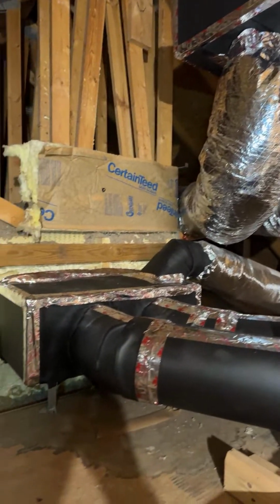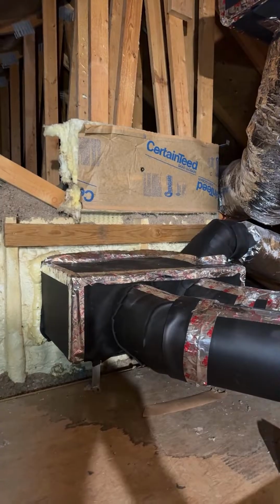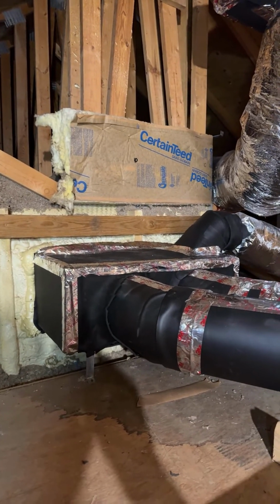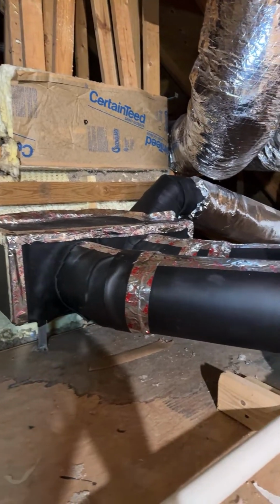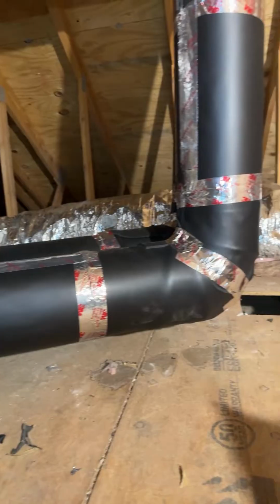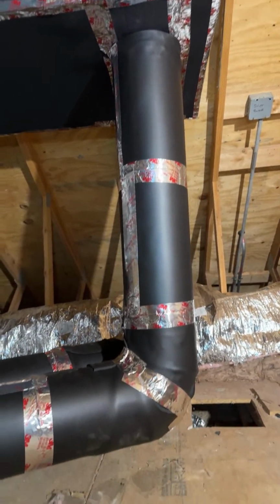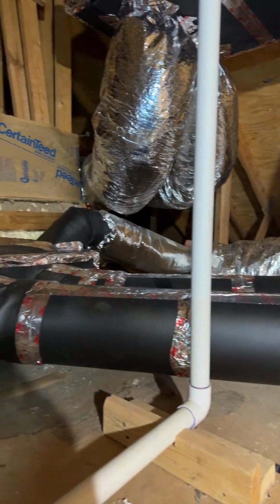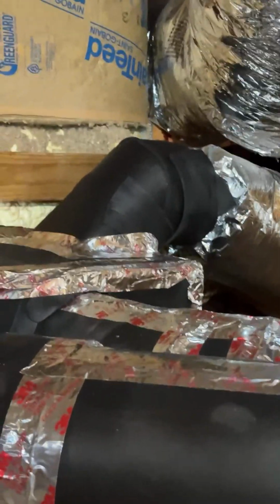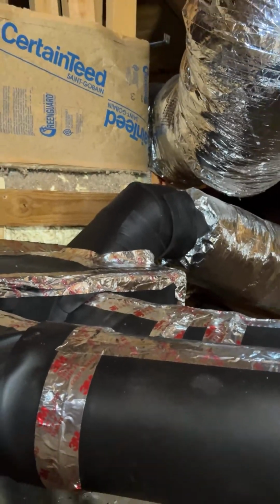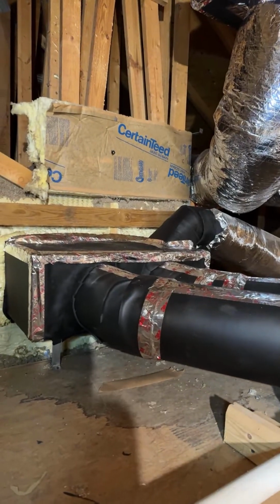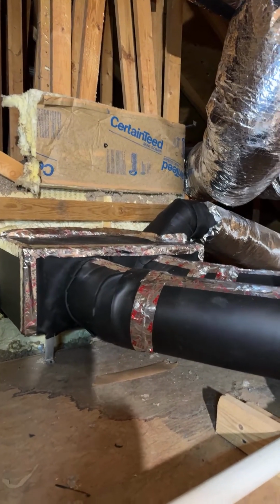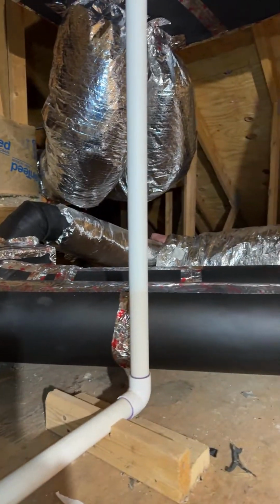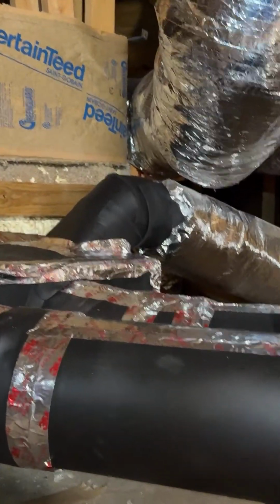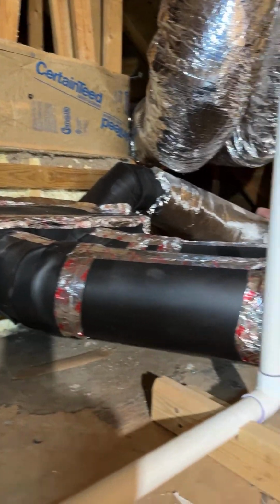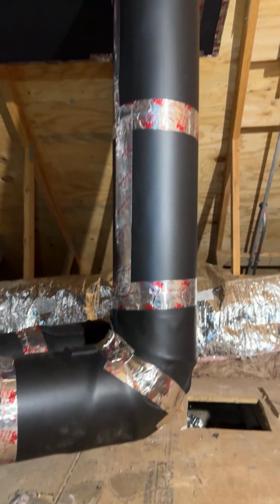And then on this bottom section, what you don't see behind this wall is a hallway. And we have a return air vent returning from this hallway. That return air goes through these ducts and goes back into the system. So in addition to this, if you watched the previous video, you also have seen that I have this section right here. That is a supply from our ERV system. That supply goes directly into this plenum here, this box, and also feeds the mini split. So the ERV is providing fresh air through this duct, and that fresh air is then getting taken into the return of the mini split and brought up to the system.